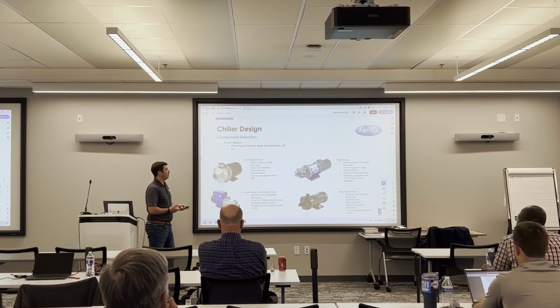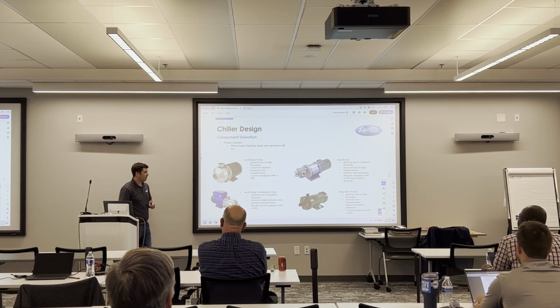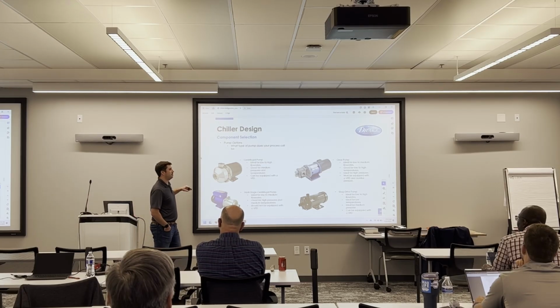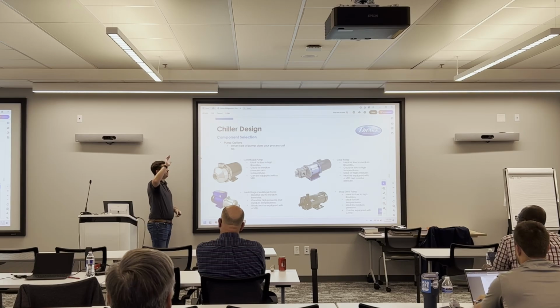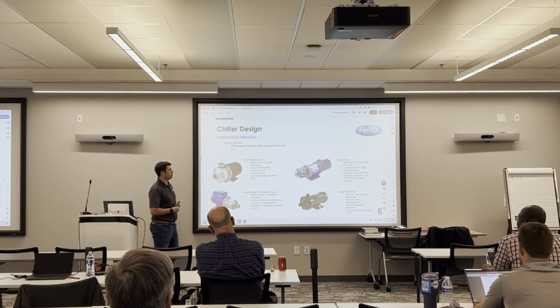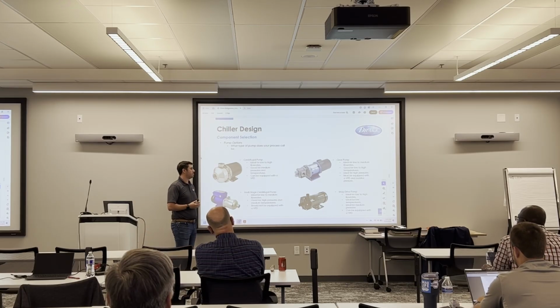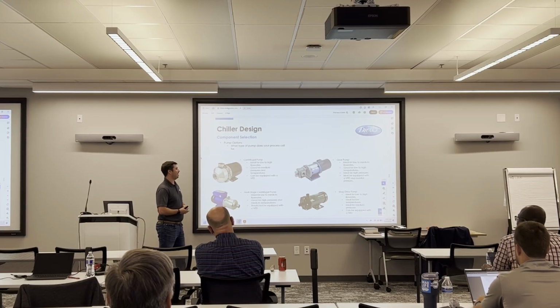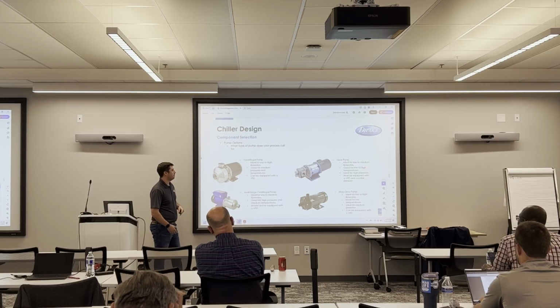We used this pump recently on an aerospace application. We put a chiller next to a rocket, and the chiller had to push fluid all the way up to the probe that they were launching into space, which was about 200 feet in the air. So we had a decent amount of head pressure to overcome. This gear pump was nice. They had a low flow rate application. All the chiller had to do was cool the flight controls. I say only, but yes, it had to push up 200 feet in the air with a low flow rate. So this was the right pump for us to use.